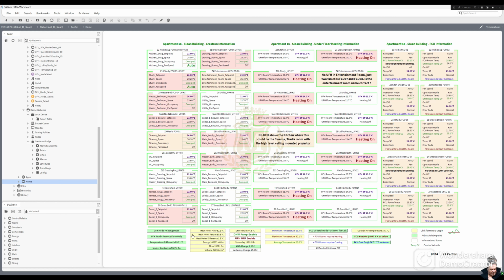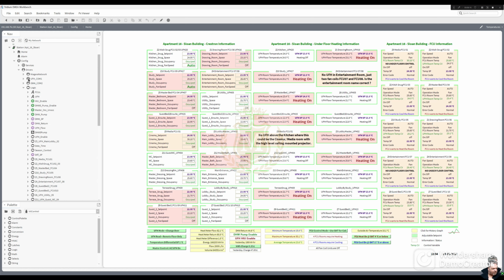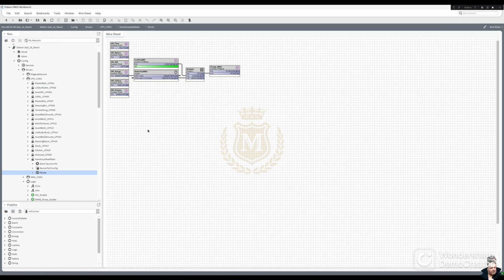And then we've got a Kamstrup heat meter there, which I'm just taking some Modbus information from, and done a bit of logic there just for taking what kilowatt hours have been used in a day. I can show you that logic. I actually wrote it in the Kamstrup heat meter page, in the wire sheet view, and I wrote it in there.